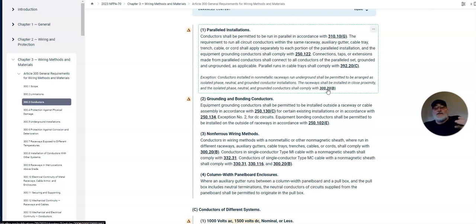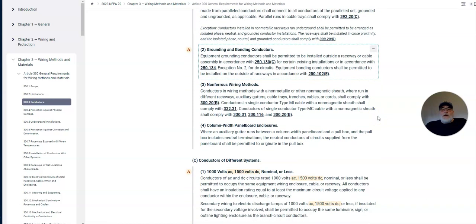So basically we're talking about a duct bank, which is a grouping of conduits underground in a concrete encasement. And we'll go on further on that. This is where you're really going to see something like this. Not very often, but this is where you're going to see this. So, nonferrous wiring methods: conductors in wiring methods with a nonmetallic or other nonmagnetic sheath, where run in different raceways, auxiliary gutters, cable trays, cables, or cords, shall comply with 300.20(B).